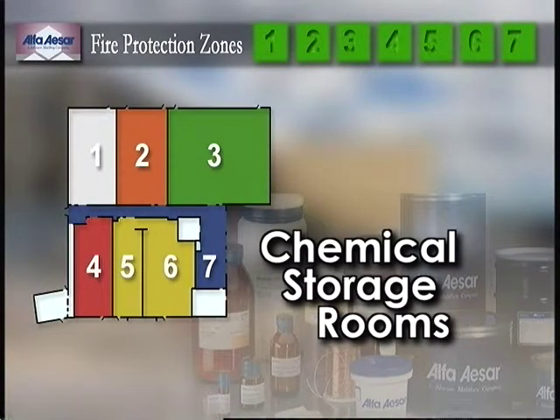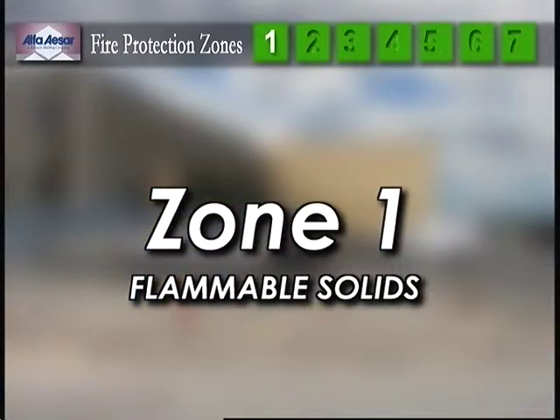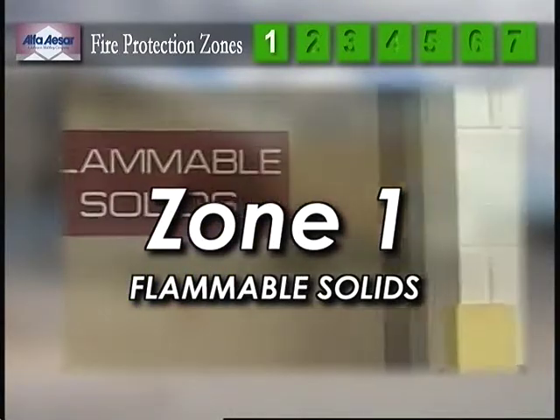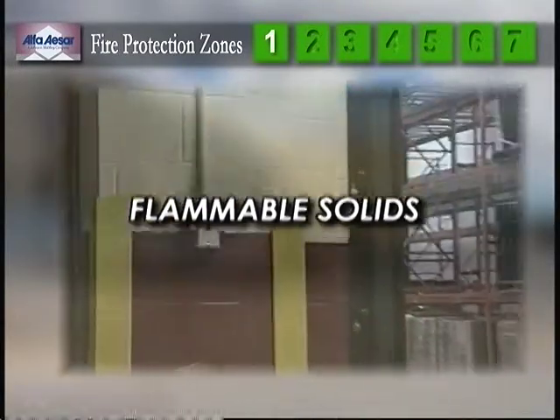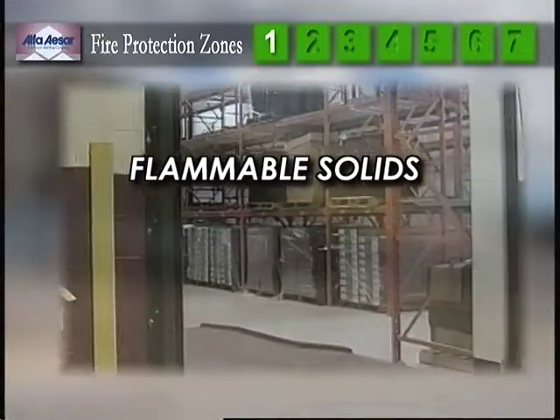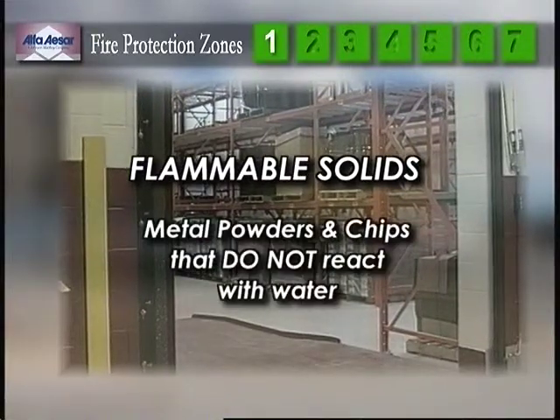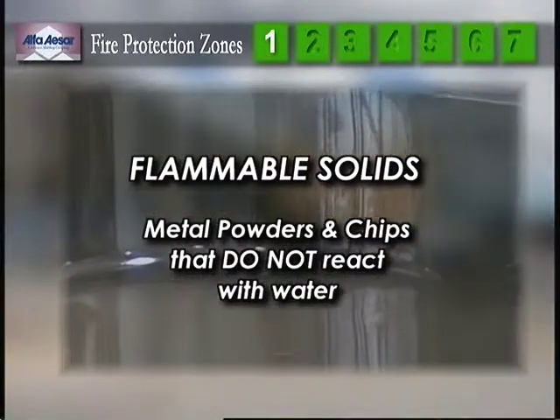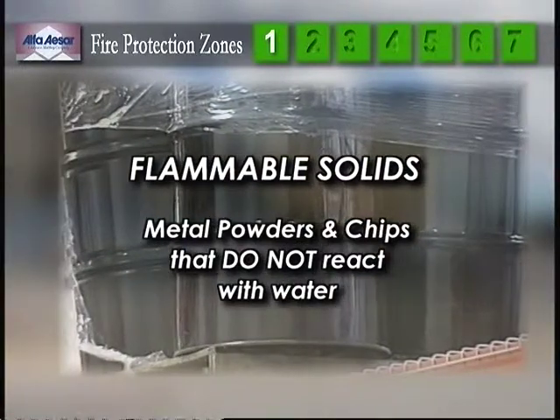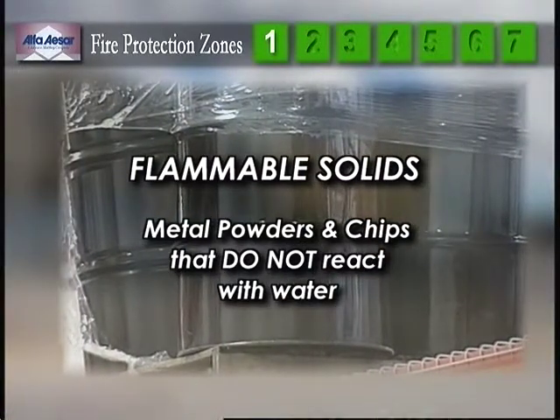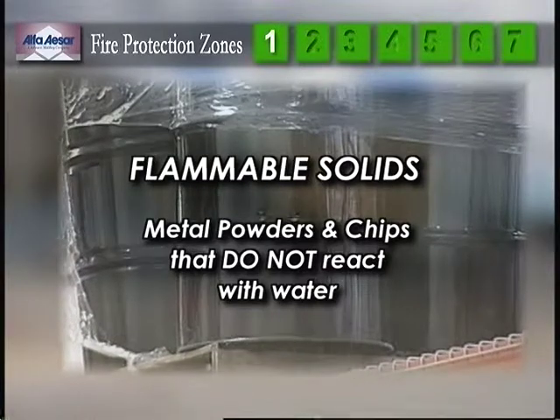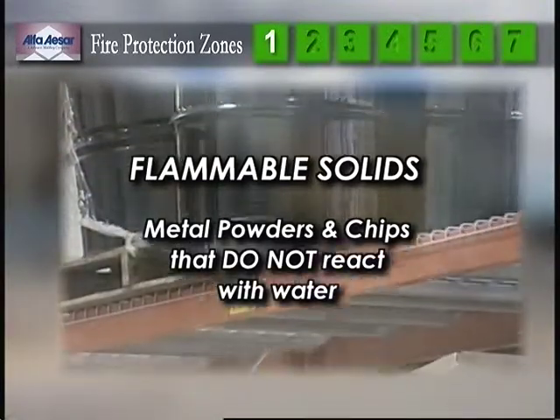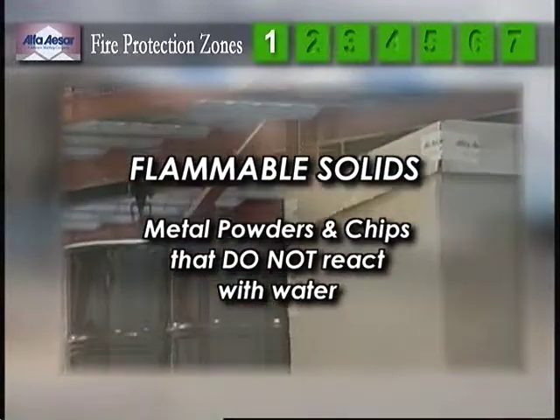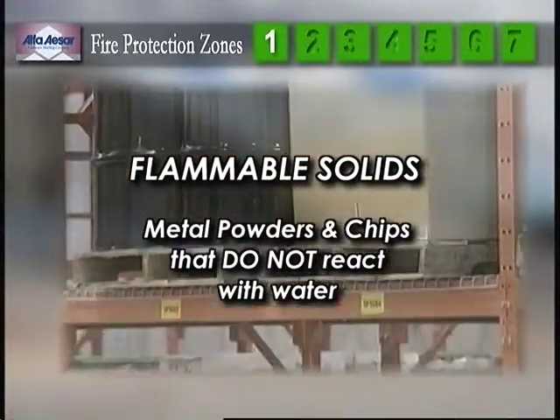Each area where chemicals will be stored or transported is separated into fire protection zones. Zone 1 is an area approximately 4,200 square feet in size, housing flammable solids. Product stored in this area is primarily metal powders and chips stored in cans, metal pails, and drums that vary in size up to 55-gallon drums. It is restricted to materials that do not react with water or have a very low reaction if in contact with water in the liquid state.